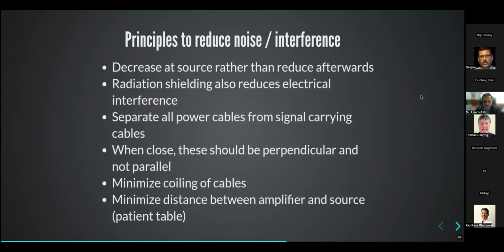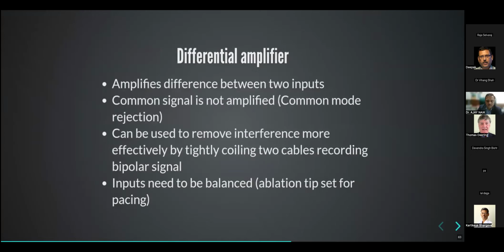And like I said before, see that your power cables and cables carrying data are kept separate. And if they have to come close to each other, make sure they remain perpendicular to each other. Minimize coiling of cables. Generally for cable organization you need to coil cables, but try to keep this minimal. And again, as we discussed, you have to minimize the distance between amplifier and source.